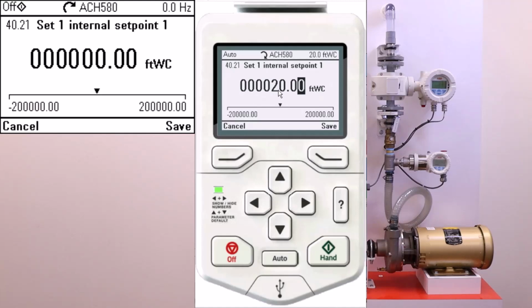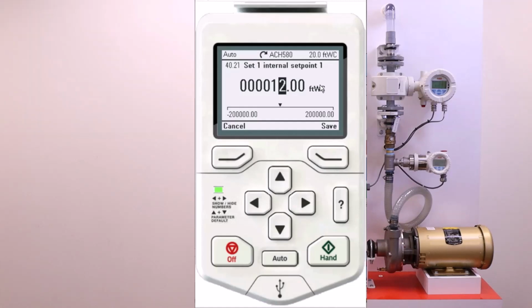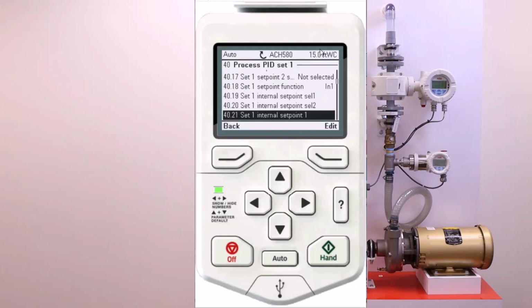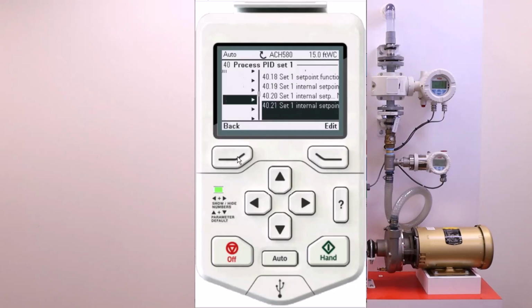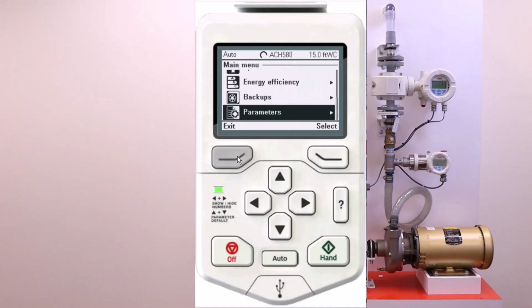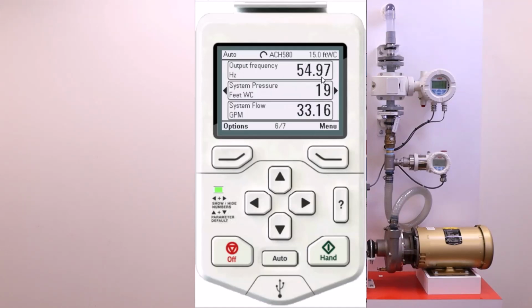If I want to change this, I can change it down to 15 feet of water column. There's 15 feet of water column. I save it. My new number up there is 15 feet of water column. My drive is now changing its speed to work down to the 15 feet of water column.